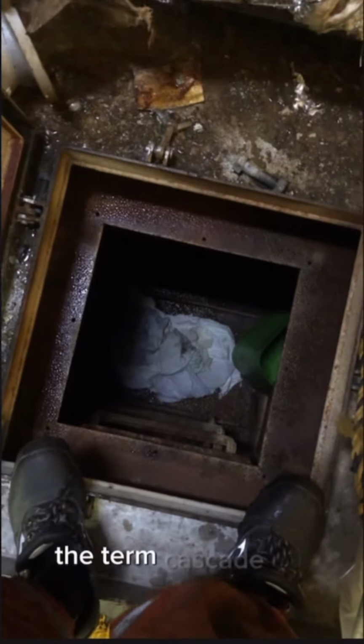The term cascade is often used because the dirty condensate is filtered through cascading method in different chambers. Dirty condensate doesn't readily have any contamination. However, due to failure of any heating coils, oil may reach the system, and it then contaminates the whole system. To avoid such situation, dirty condensate is treated in cascading process.